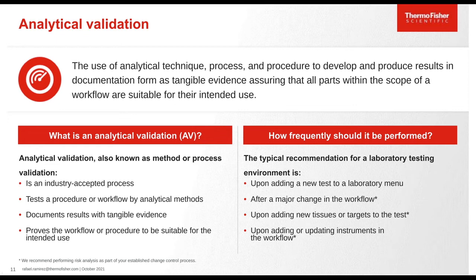An analytical validation is the use of analytical technique, process, and procedure to develop and produce results in documentation form as tangible evidence assuring that all parts within the scope of a workflow are suitable for their intended use. You should be performing a validation any time you're adding a new test to your menu, adding a major change within your workflow, changing sample types from say urine, tissues, or swabs, or even adding a new assay to your panel.